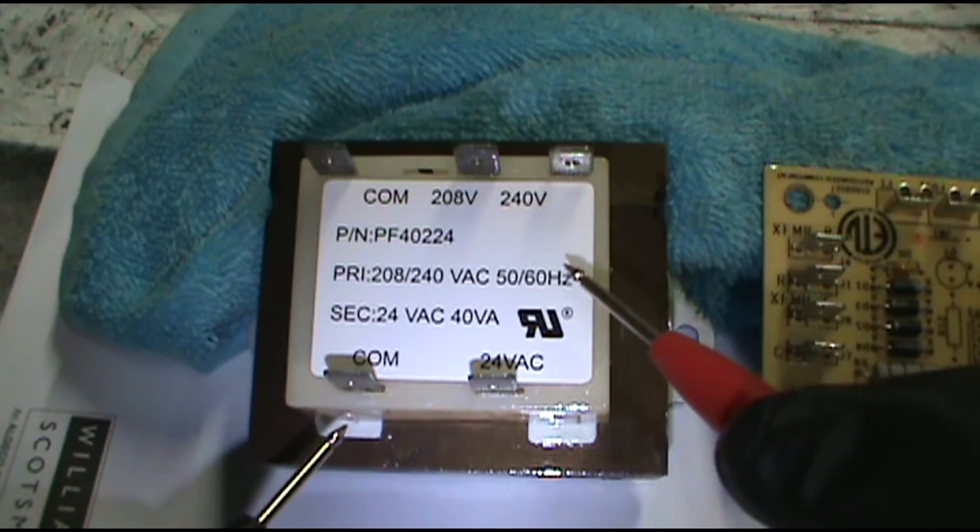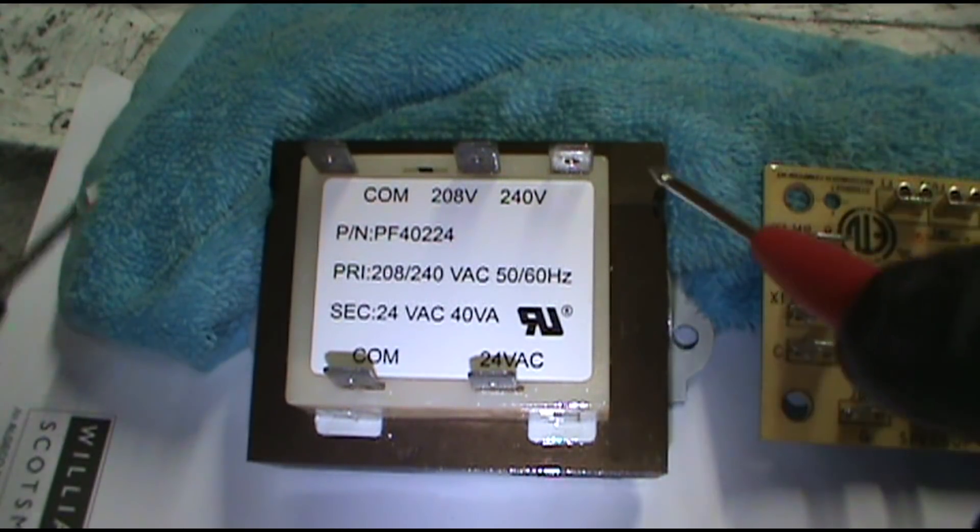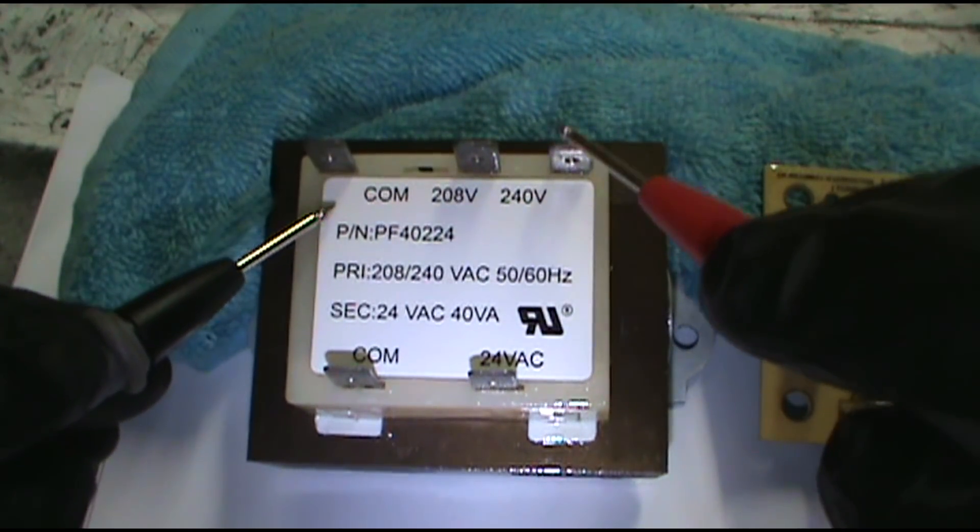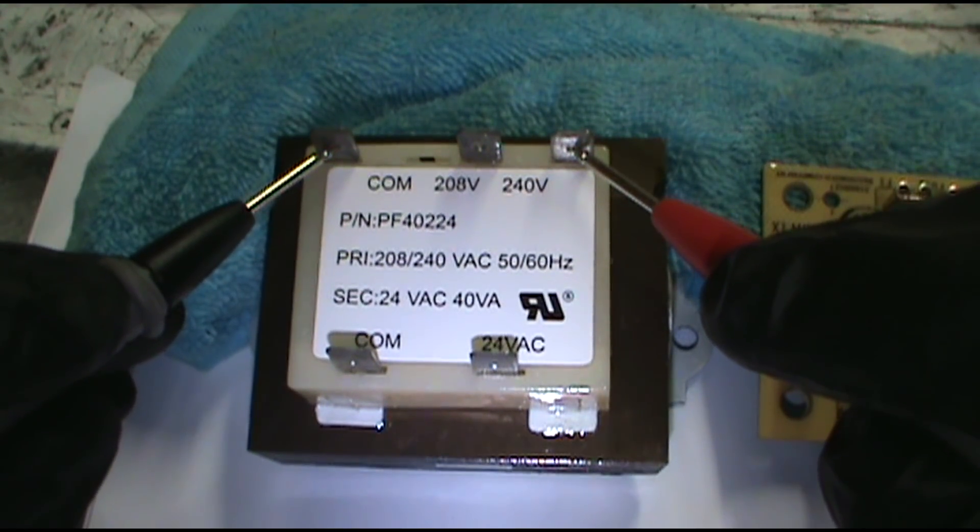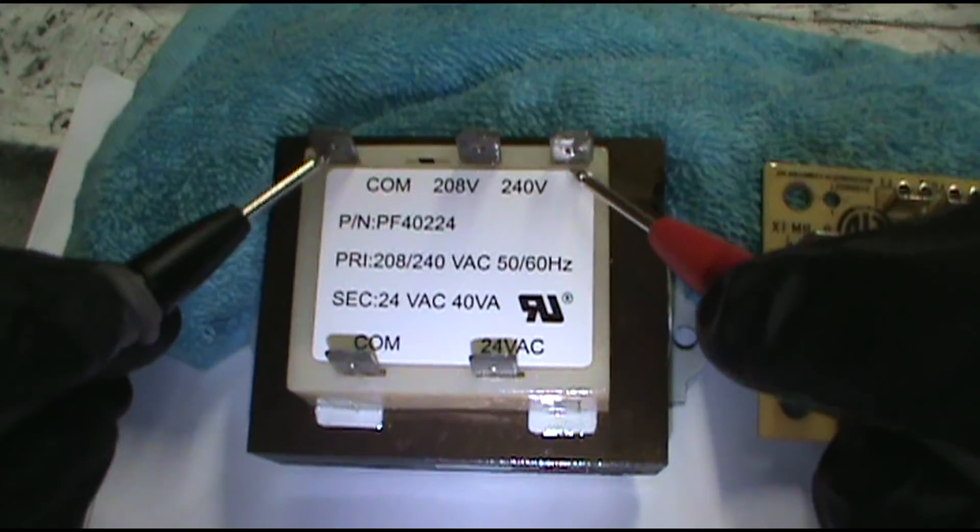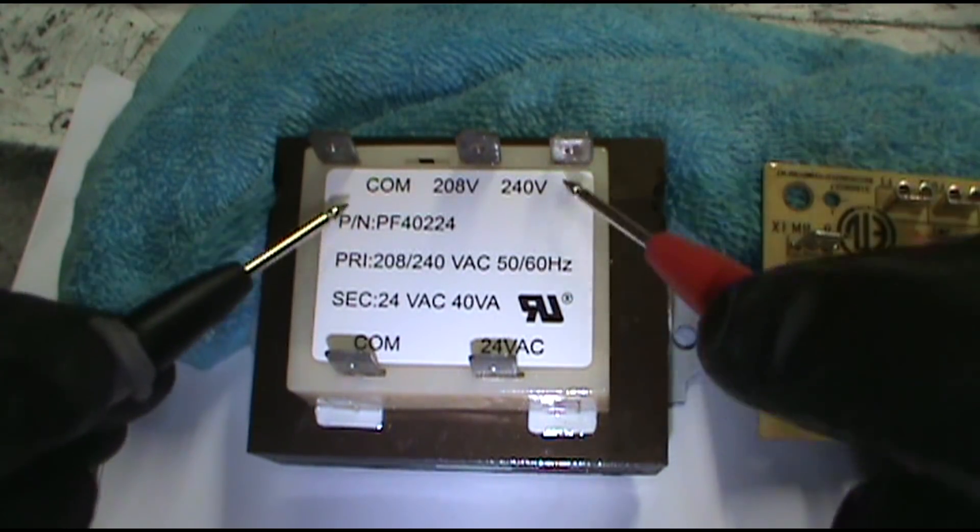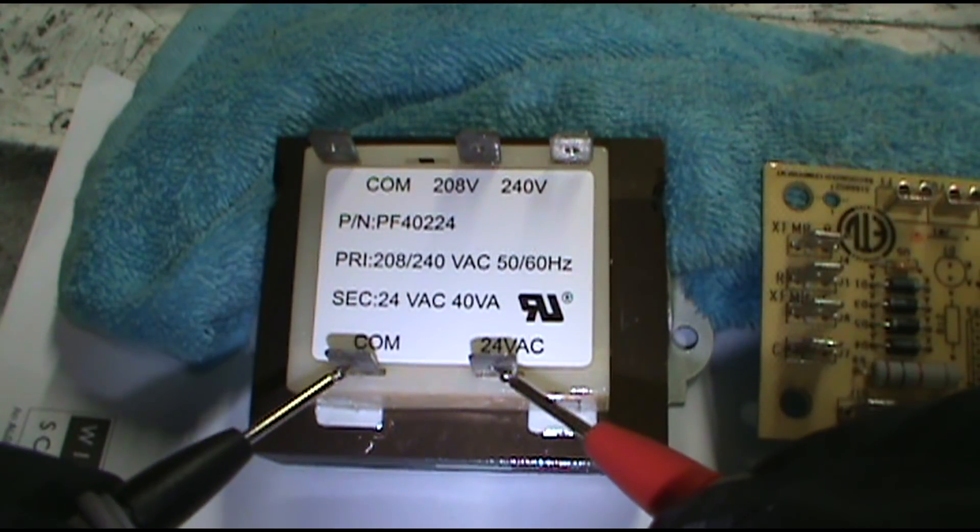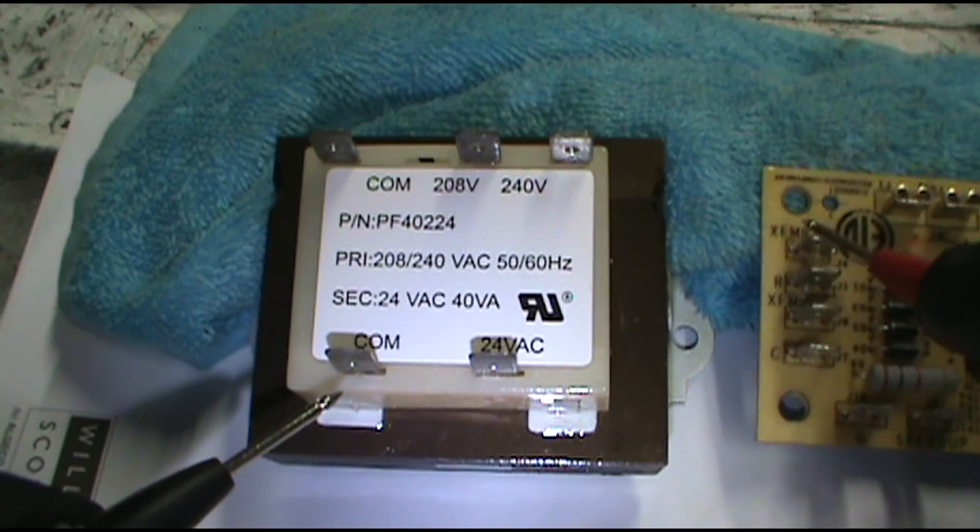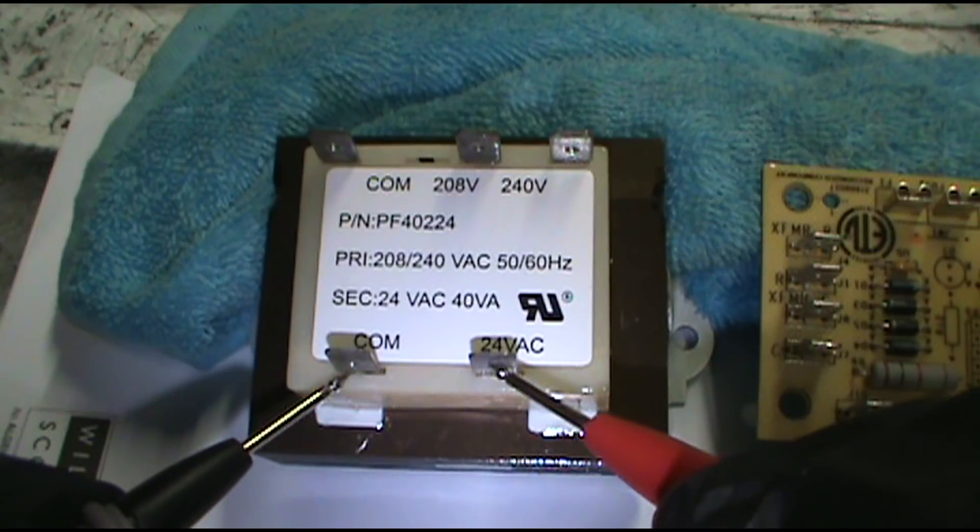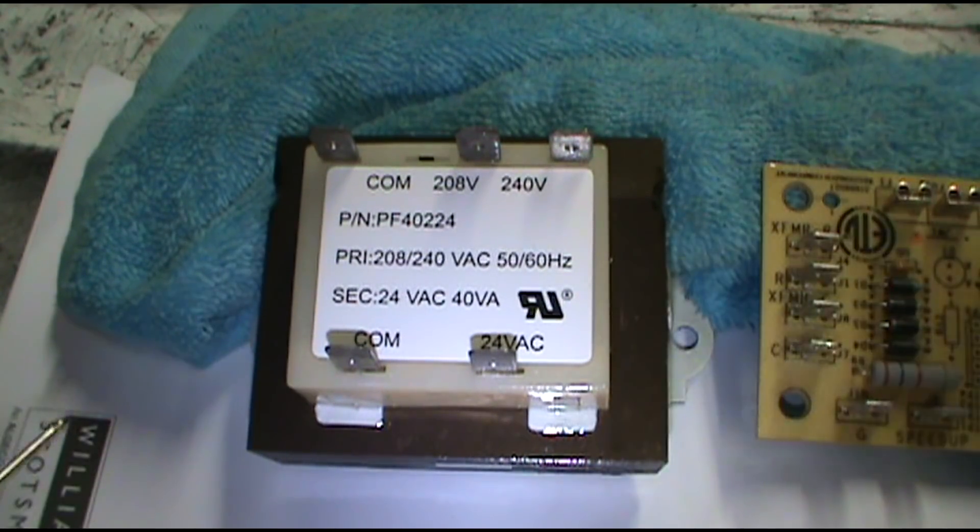This is the high voltage, this is the 240 coming in off the lug. Touch here and here, you should have 240. This just transforms the power into 24 volts. You should have 24 volts coming out of here and into the board. So if you don't have 24 here, change out the transformer.